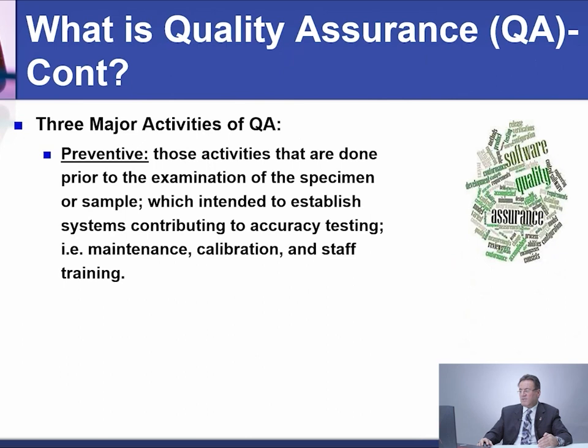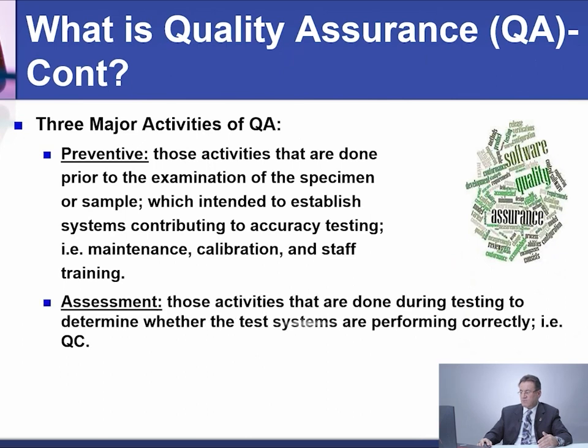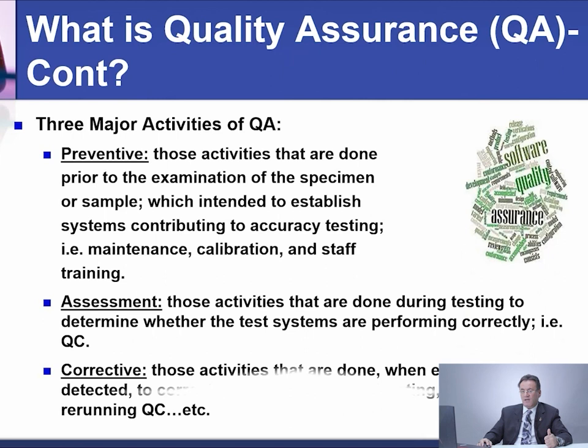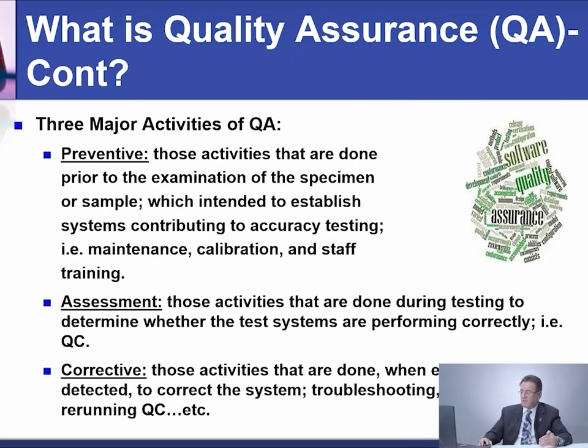There are three major activities of quality assurance: preventive, assessment, and corrective. The preventive activities are those done prior to the examination of the specimen or sample, intended to establish systems contributing to accuracy — like maintenance, calibration, and staff training. Assessment activities are done during the testing of the specimen to determine whether the test systems are performing correctly, like QC.